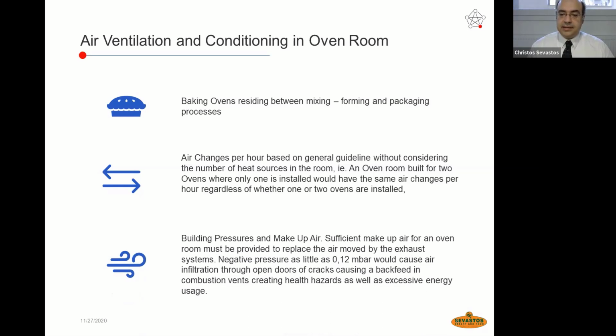Building pressures and makeup air. Sufficient makeup air for an oven room must be provided in order to replace the air moved by the exhaust systems. Negative pressure, which is often the situation in such areas of tunnel ovens, as little as 0.12 millibar, would cause air infiltration through open doors and cracks, causing a backfeed in combustion vents, creating health hazards as well as excessive energy usage. This is the most important thing which should be considered in terms of the design of an oven room. Generally, oven rooms having tunnel ovens or rotary ovens or whatever kind of heat source appliances.